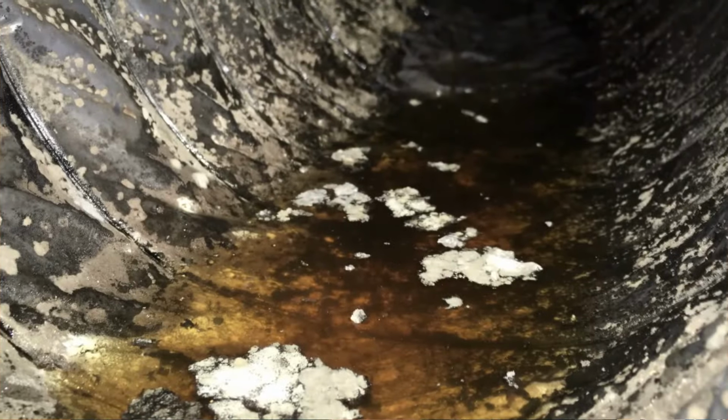You know, sometimes you're going to catch it, sometimes you're not. And if you don't know what's going on inside your ductwork until you get someone down there to really look at it. With this one, what we have to do to fix this is we have to cut out that duct. We have to pull a new duct, connect it. We have to assess the damage and see if there's any rust. I mean, obviously there's going to be some biological growth going on inside there that nobody knew about. And this could be you.